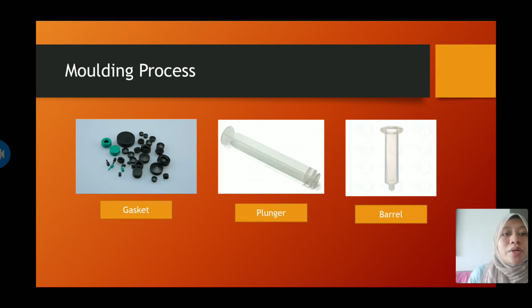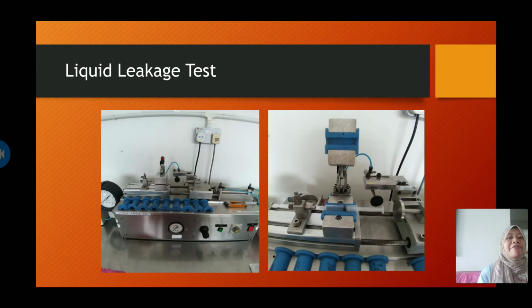In this molding process, the only thing I did was the liquid leakage test. The molding machine continuously produces the gasket, the barrel and the plunger, and every 2 hours I come to the machine and take about 30 samples, and I do the liquid leakage test. I fill the syringe with liquid color and put it on the side of the machine. This is the machine for the liquid leakage test. Then the machine presses the syringe at about 300 bar for 1 minute.